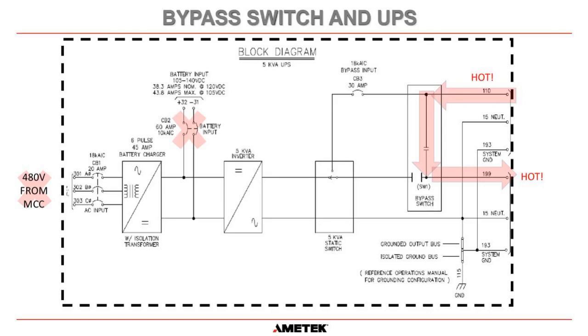So this isn't a single line. This is more of a wiring diagram for one of our UPSs, but it's the same thing again. What we're saying here is that the 480 is off, and if we disconnect the battery, wires 110 and 15 are hot, and wires 199 to 15 are hot.